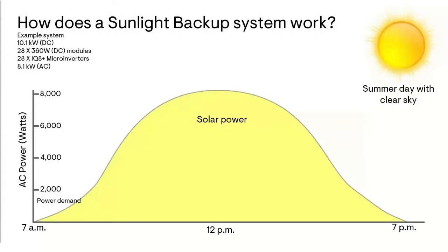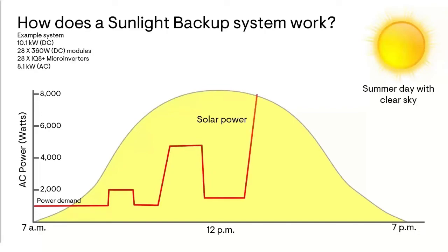A key difference between a sunlight backup system and one with batteries is that it doesn't have the ability to provide an extra burst of power. We know this as peak power with battery systems. It can't do that to help start appliances that have a starting surge, like air conditioners and pumps. If an air conditioner were to turn on, the large demand spike would most likely cause an instant collapse of the microgrid.